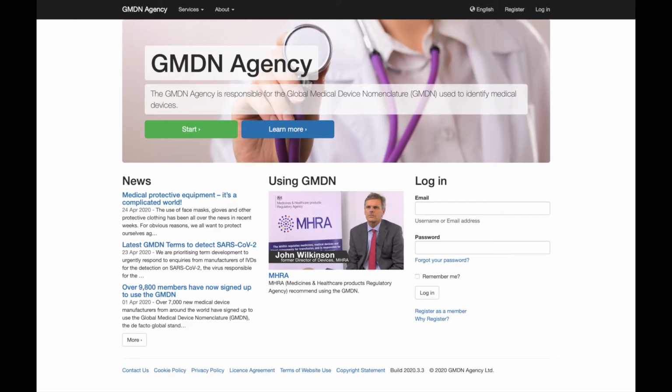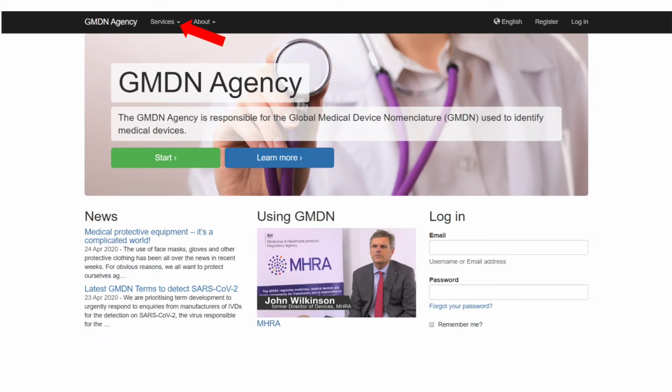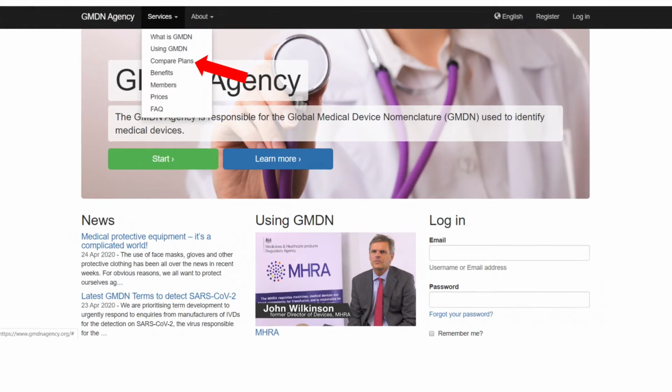So to get a GMDN code for your purposes for FDA GUDID compliance, you'll need to go to the GMDN agency website and sign up for one of their accounts to access their codes. So the first step would be to go to the GMDN agency website. You can sign up for an account by clicking the services button on the top banner. That'll bring a drop-down menu and you can select compare plans.